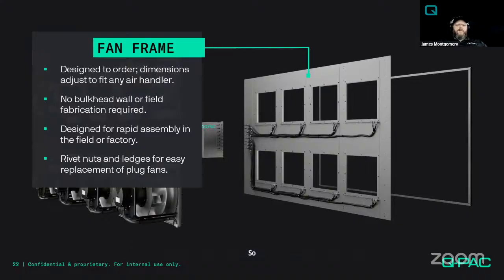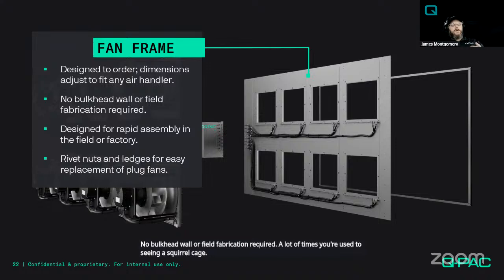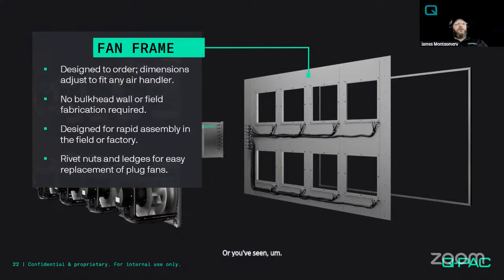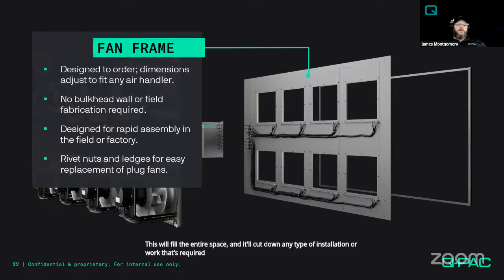So the fan frame, again, we talked about this, designed to fit any air handler. No bulkhead wall or field fabrication required. A lot of times you're used to seeing a squirrel cage, or you've seen a large inline axial motor, and then there's some kind of connection point and then a bulkhead wall. No longer is that required. This will fill up the space. There's no sheet metal fabrication or anything. So as long as we have the correct measurements, this will fill the entire space and it'll cut down any type of installation or work that's required. This thing can just drop right into a system.